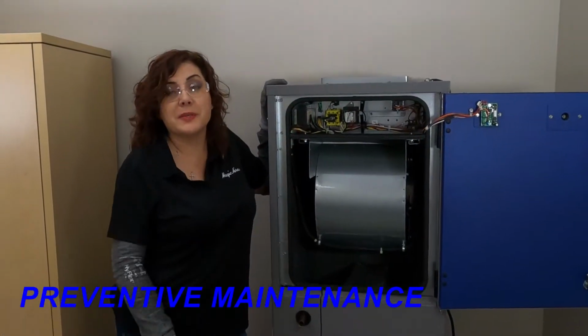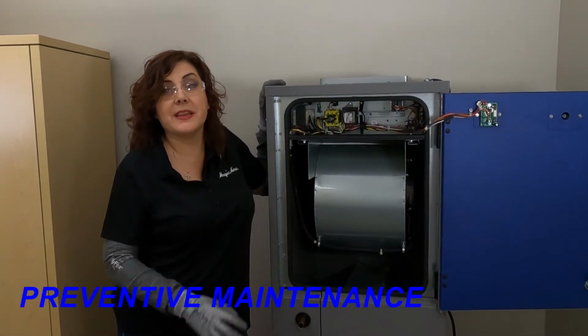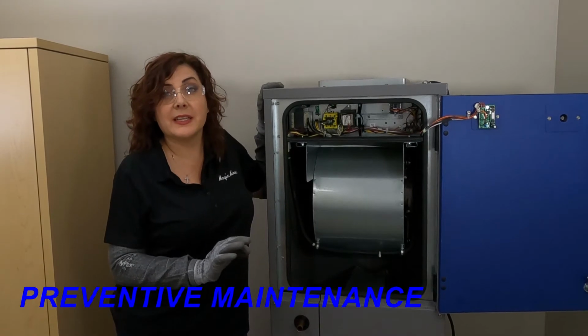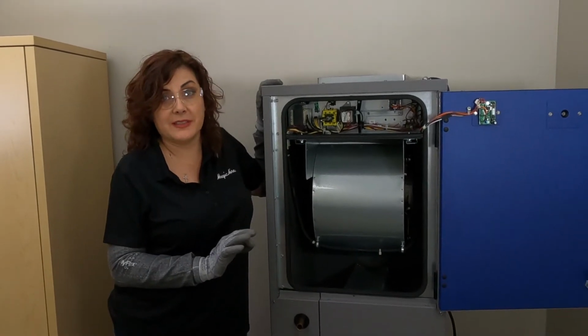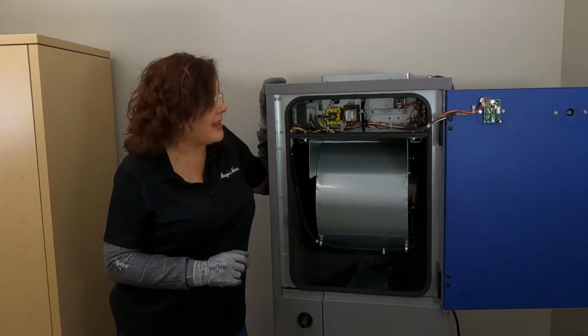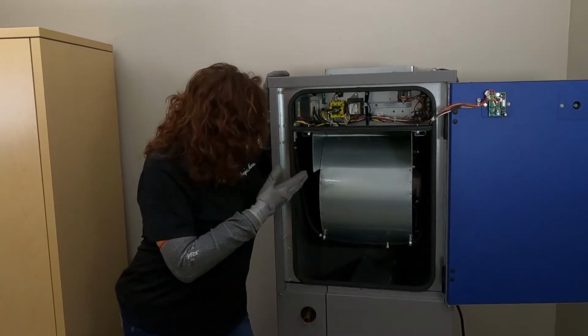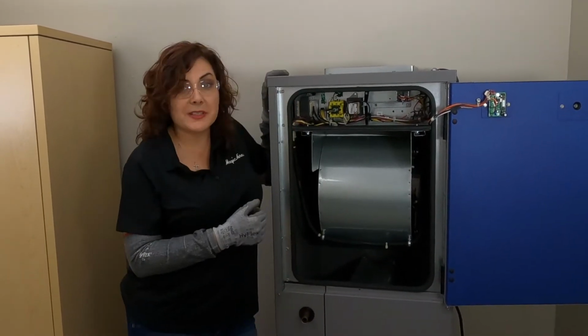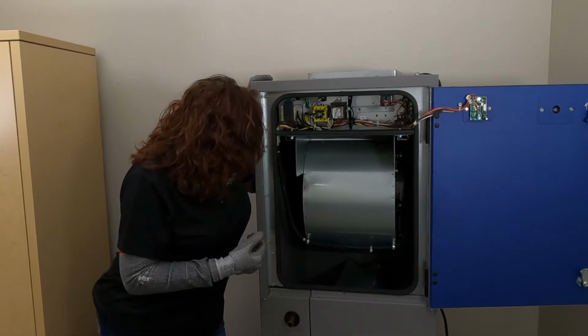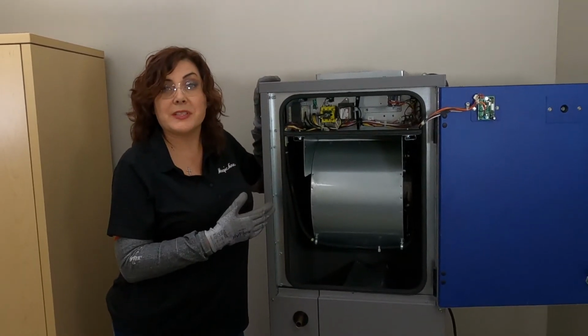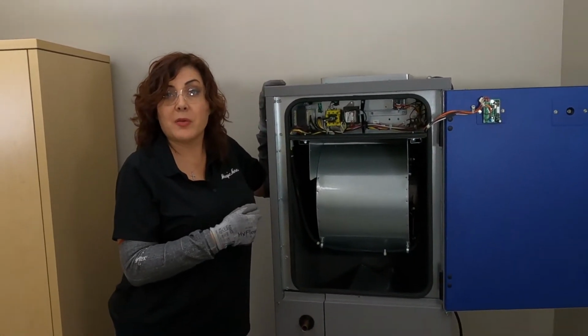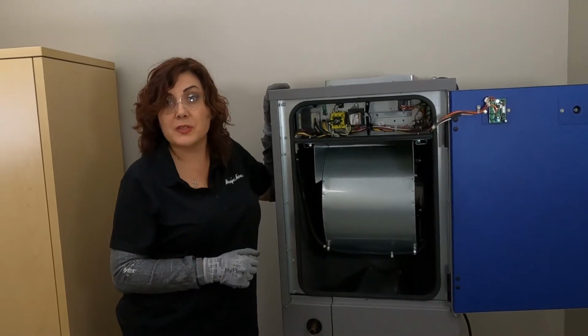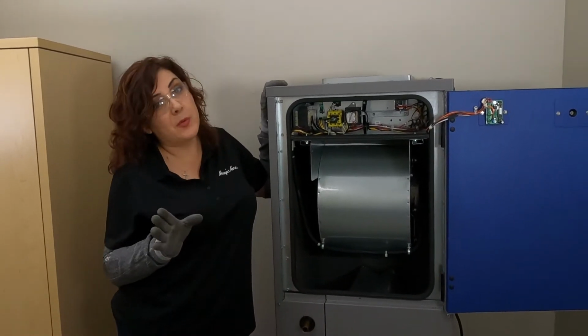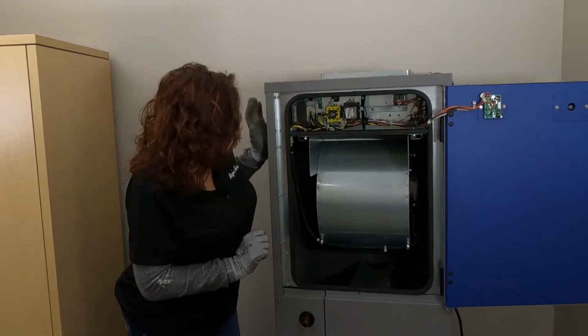The first item we're going to be talking about is preventive maintenance, the items that you will need to do periodically as your particular unit needs it. One of the first items you're going to look at is the blower wheel. Is it dusty? Does it have a lot of contaminants on it? One of the items that you can do is you can blow it with compressed air or use a vacuum or a brush to knock off most of the dirt. I wouldn't recommend washing it because that's a pain to clean up.